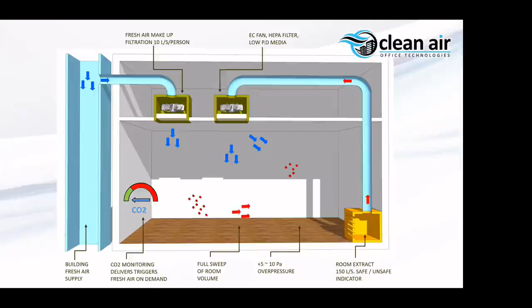Now, there's a quick aside here. I was going to say it's quite a dead end, but it's a blind alley that we've salvaged something from. We found a company in Switzerland, is it Switzerland? Yeah, Switzerland, that are manufacturing a particle counter. Now, typically when we validate labs, we're using particle counters that weigh a lot and cost tens of thousands, but are calibrated. But we found a company producing particle counters the size of 2 matchboxes. So we thought, well, how can we use that? Could we link this to fan speed and use that to directly control the airborne particulate challenge? What we found was that offices have many different sources of contamination. So it's not just particles coming from people. You've got carpets, you've got walls, you've got ceilings that are acoustic tiles, and the shedding.